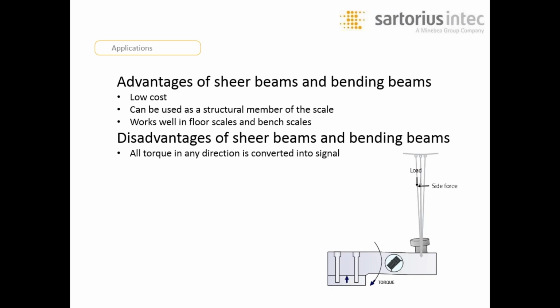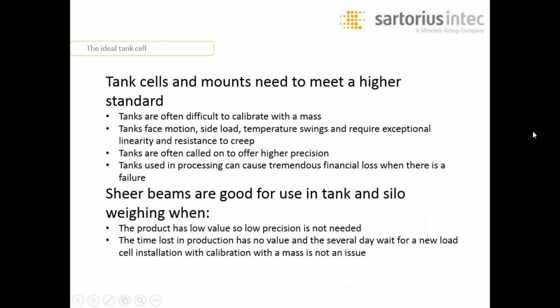Every calibration is unique and must be done by spanning a mass, meaning you must apply full load to the scale in order to completely span and know what the millivolt signal would be back to the digital indicator. And most importantly, not optimized for resistance to creep. They have inconsistent metallurgy. Tanks have a constant load, not like a bench scale that is loaded and unloaded. Not optimized for drift. Inconsistent gauges. You can have a lower millivolt per volt output signal, creating erroneous signals that way. Most importantly, in a shear beam load cell, when used in a tank application, any force applied to that load cell, whether it be vertical, horizontal, or any kind of rotational torque, is all applied to the cell and will cause a change in weight value.